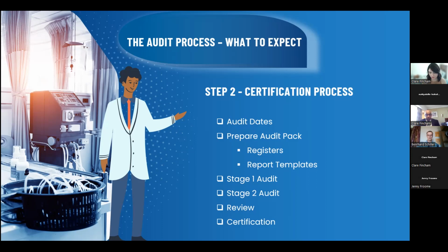And here we do traceability on all, or not all, but on a sample of medical device transactions. It's important to identify what your critical control points are. How do you manage product recall, for example? How do you handle quarantine product? How do you handle non-conforming product? How do you validate your processes, etc.?